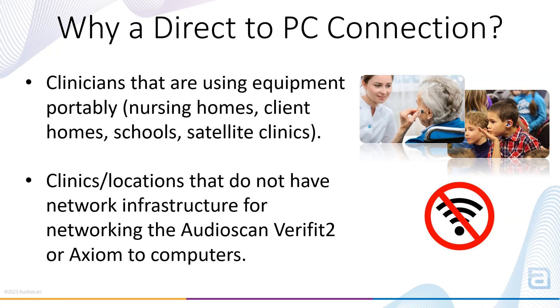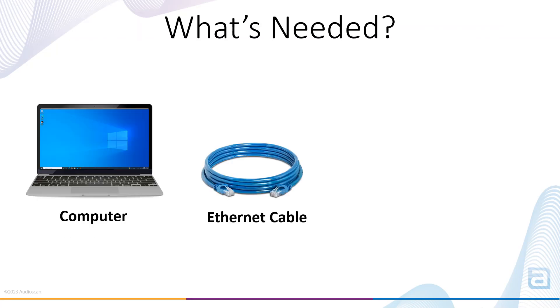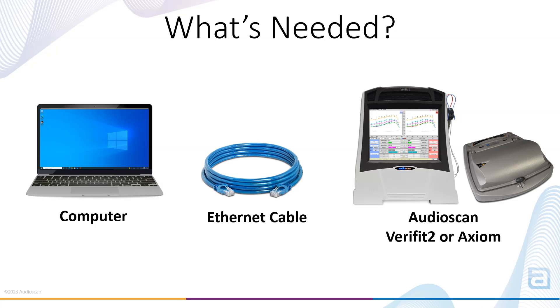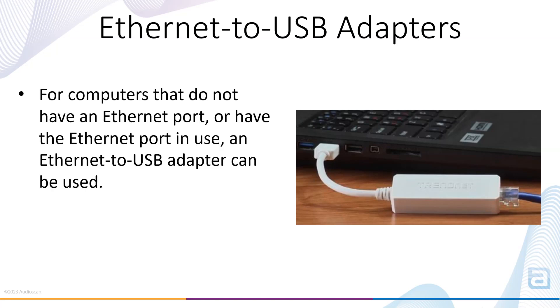A direct-to-PC connection may be helpful for clinicians that are using equipment portably. It can be handy to have a network connection at these facilities, where otherwise it would not be available. The AudioScan Verifit 2 and Axiom utilize link-local addresses, also known as automatic private IP addressing for this feature, enabling a unique individual network that allows your computer and the AudioScan Verifit 2 or Axiom to exchange data without connecting to a conventional network. Simply plug the Ethernet cable into the computer's Ethernet jack and the AudioScan Verifit 2 or Axiom's Ethernet jack. For computers that do not have an Ethernet port, or for computers with a jack that is already in use, an Ethernet-to-USB adapter can be used for connecting to the PC.